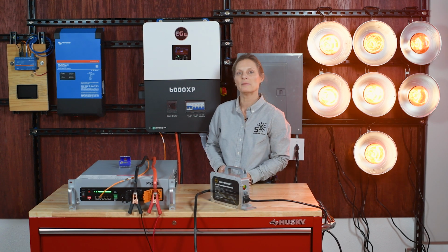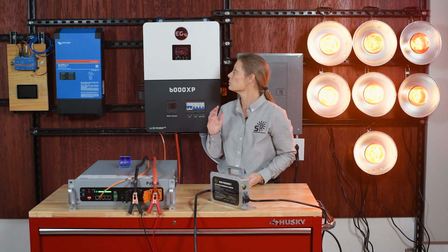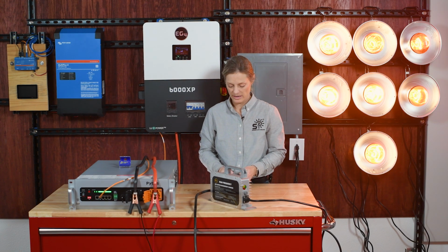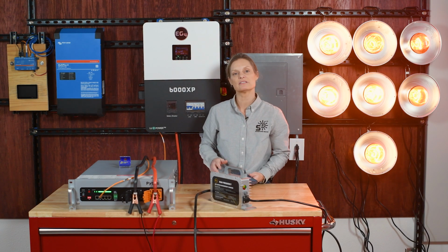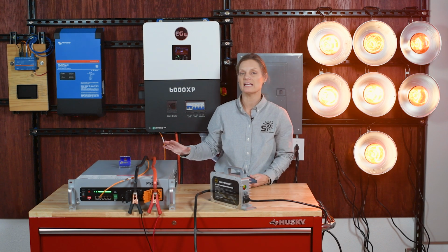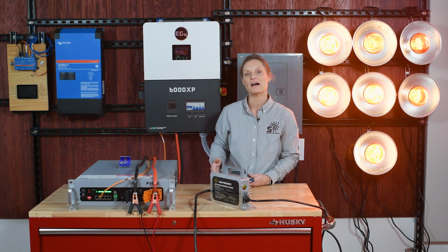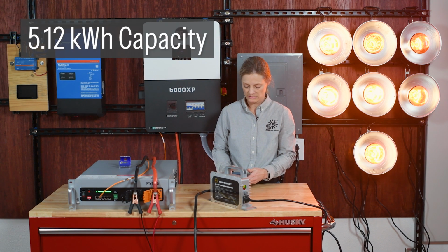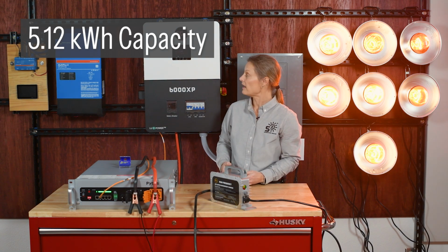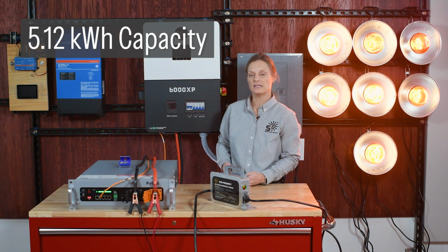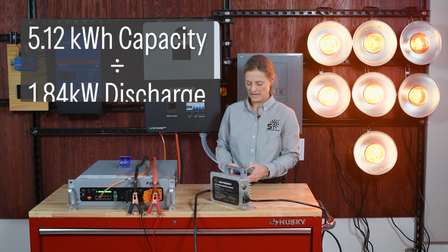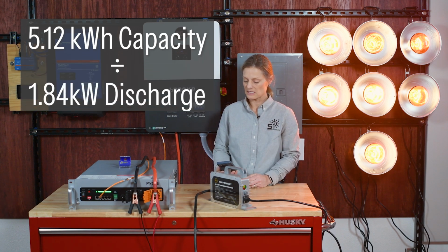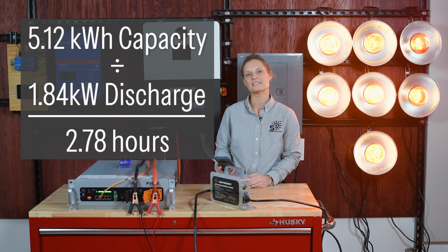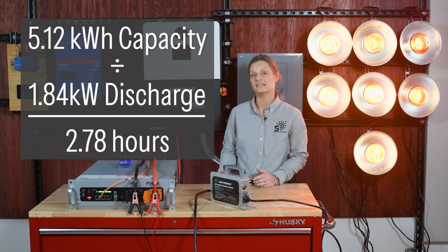Okay, it's settling in at about 1.84 kilowatts, or 1,840 watts. So to estimate the time it's going to take to discharge this battery, we can take its capacity at 5.12 kilowatt hours, and we're going to divide that by the kilowatts that it's going to be discharging, 1.84. And it tells us it's going to take about 2.78 hours. That's about 2 hours and 45 minutes.